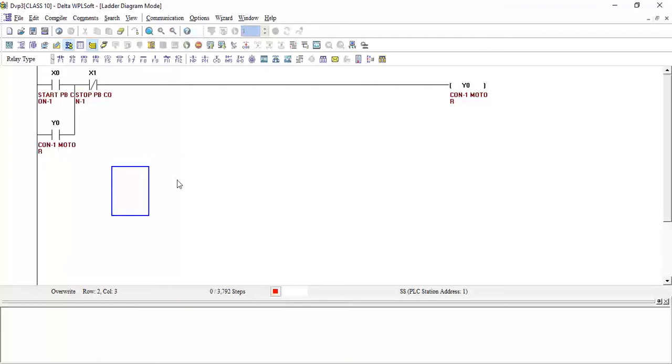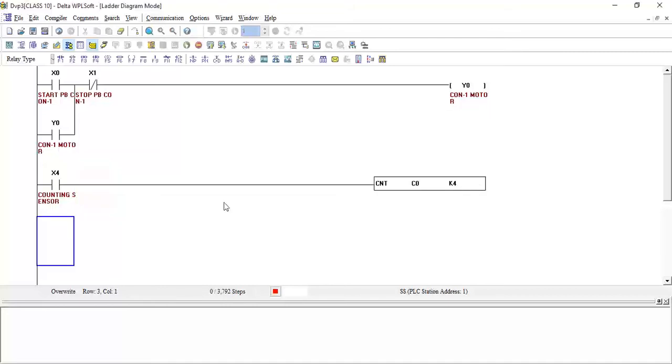So now for conveyor 2 we need to make the counting ladder. What we will take? I will take here X4 for the count, click OK. And I will take now counter CNT C0 K4. CNT is for counter, C0 is the counter number, K4 is the number of counts which is 4. Click OK, so the counter is added.